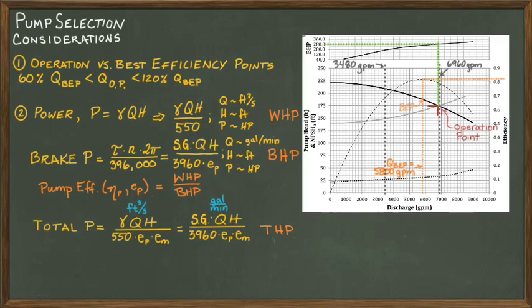We want to know the total power required to run our pumps so that we can determine the operating cost. One horsepower is equivalent to 0.746 kilowatts. Power costs are typically listed as how many dollars per kilowatt hour, so finding the cost of operating the pump is just a simple conversion problem once you know how to compute the pump power. I will cover an example of how to estimate pump operating costs in a separate video.